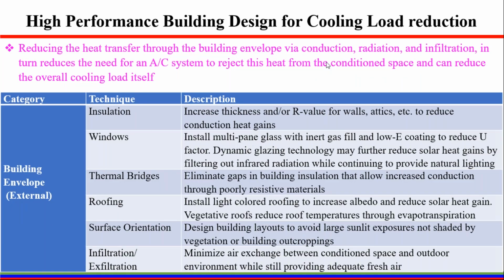Before selecting your air conditioner, we can reduce the cooling load by reducing the heat transfer through the building envelope by conduction, radiation, and infiltration. That can reduce the need for the air conditioning system to reject the heat being introduced into the conditioned space, and can reduce the overall cooling load and the air conditioning requirements. For example, if your building is not insulated, you may need much more air conditioning, and if your building is insulated, you can reduce the cooling load. The insulation can be increased by increasing the thickness or the R value of the walls to reduce the heat gains from outside.